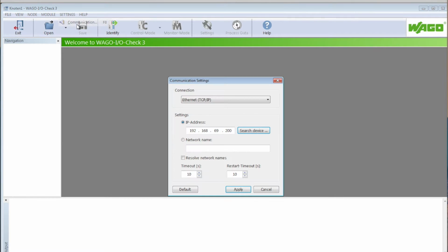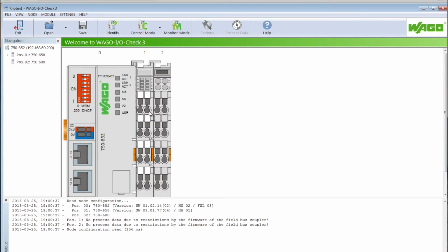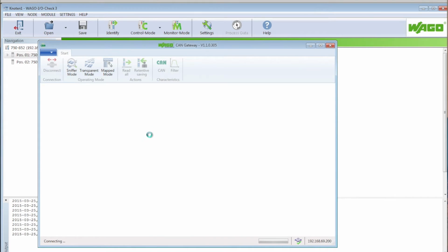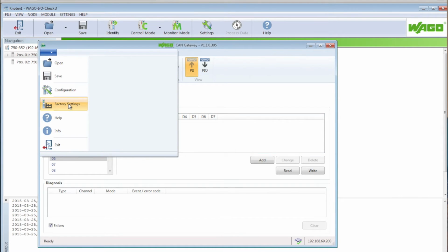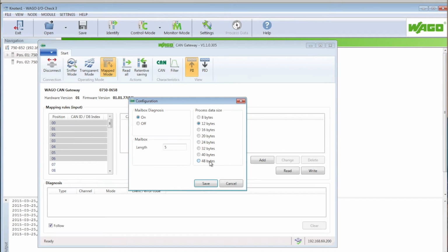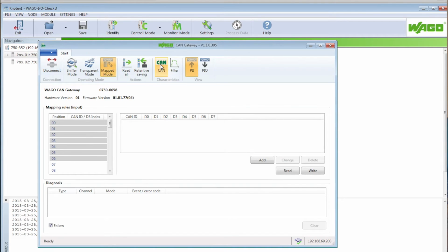Once we establish communications with I/O Check, we will identify the node, and you'll see all the modules on here. We just have the 658, so we'll right click there and go to settings. In the top left drop down menu, these are the master settings for the module itself. We'll go to configuration and see we have up to 48 bytes that we can map for the process image.